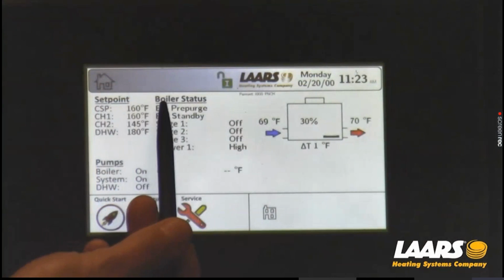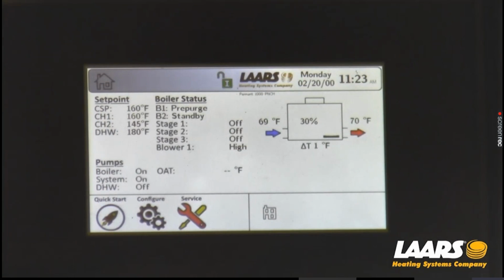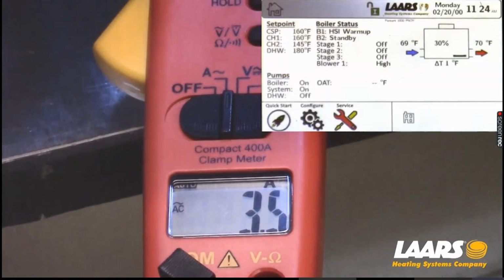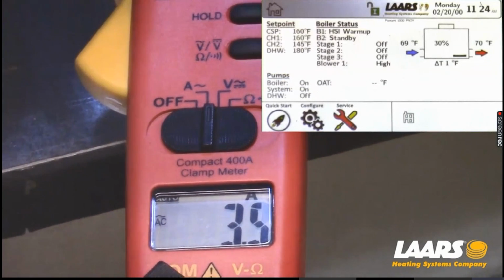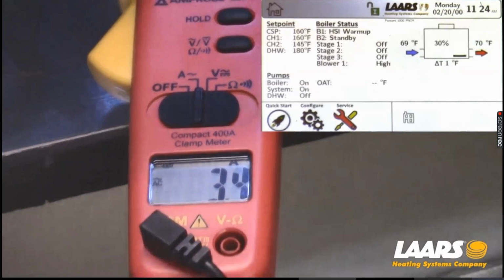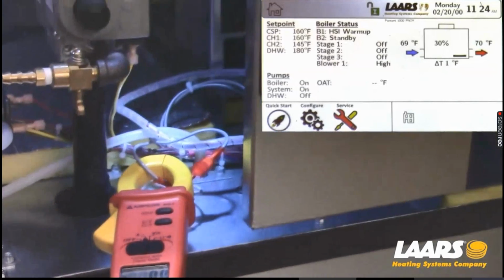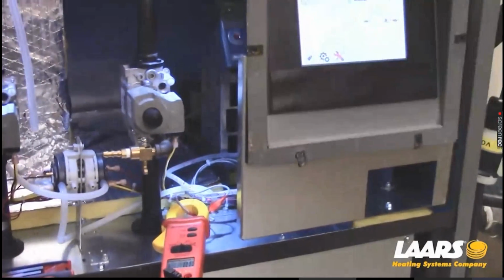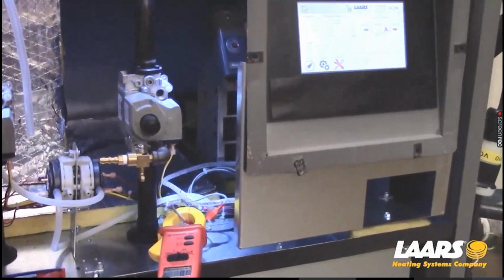So currently we're in pre-purge. It's going to tell us everything that's going on with the boiler. Once we pre-purge the chamber, the next thing that will happen is we're going to HSI, hot surface ignition. Yes, as you can see, we're running about 3.5 amps. A good igniter runs between 3.4 and 4.2. If you have a weak igniter, you want to replace it with anything less than that.